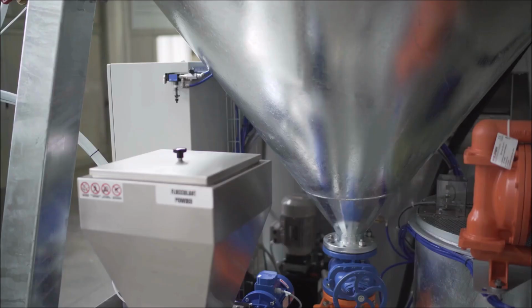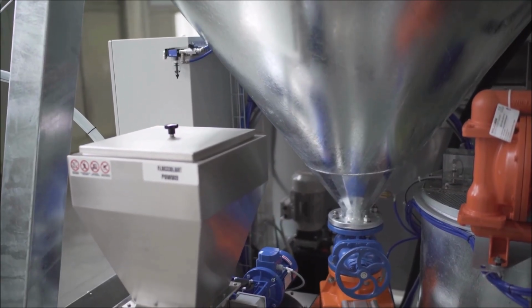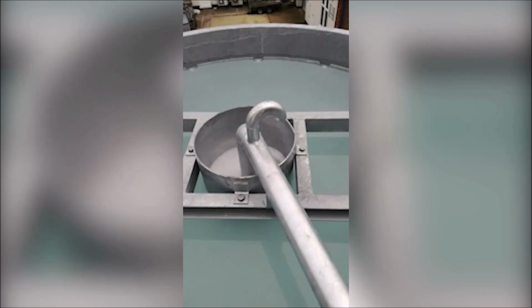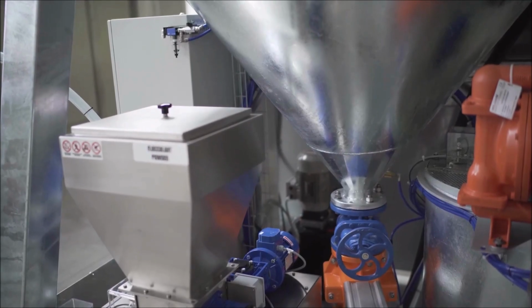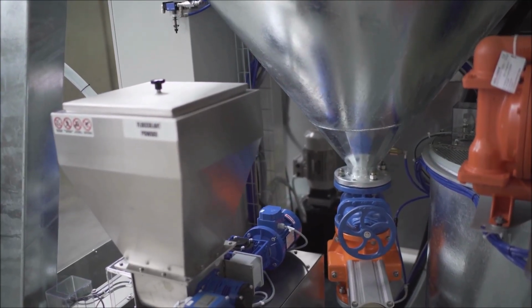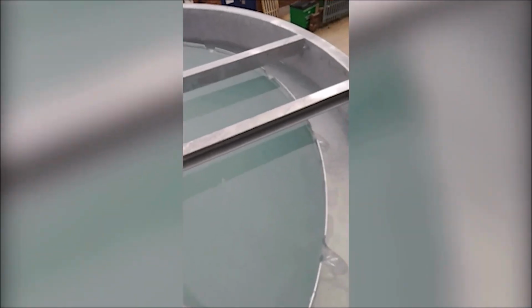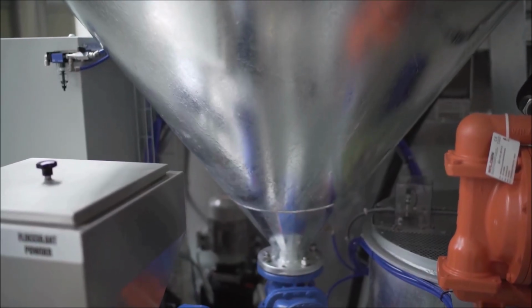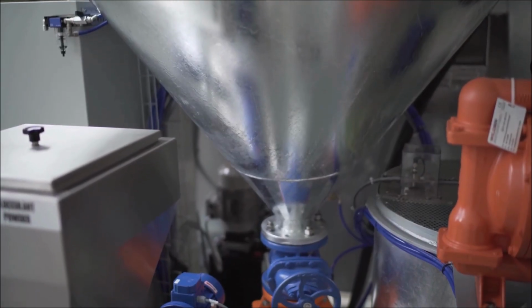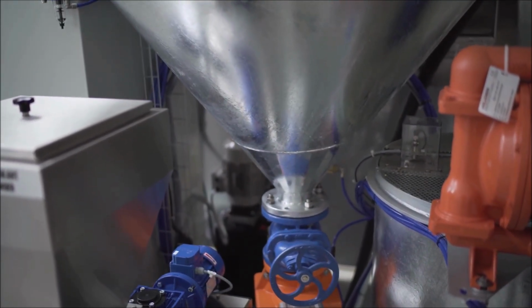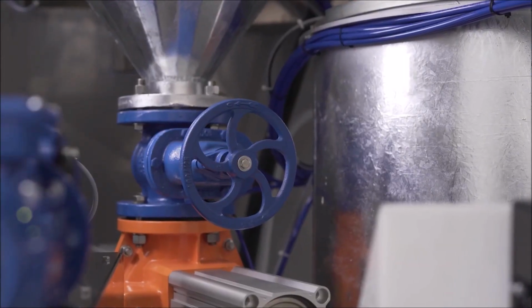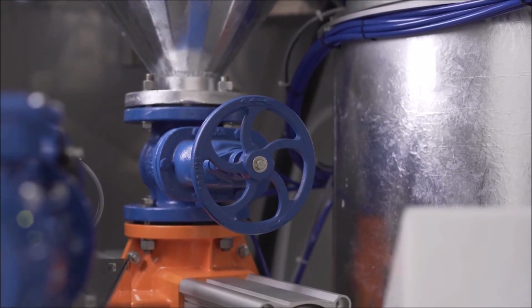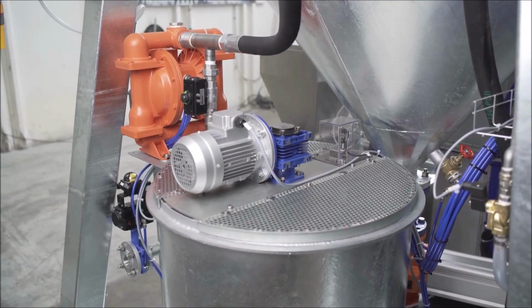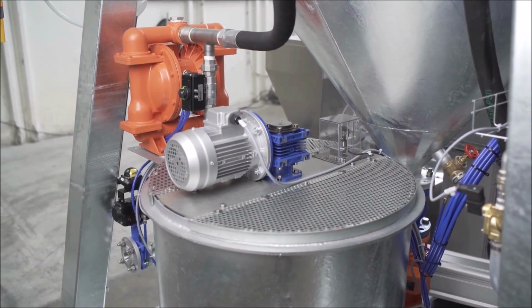This clarification process allows us to obtain a compact sedimentation of the sludge at the bottom of the decanter. At the same time, in the upper part, only the clarified water remains, which through the overflow hole is conveyed to a special storage tank. This water is then ready to be brought back to the machines installed in production. The sludge accumulated at the bottom of the decanter is ready for the second process managed by the plant, namely dehydration with filter press. Through a pneumatic valve, the sludge is discharged in a completely automatic and controlled manner and is conveyed to a dedicated tank, where an agitator ensures proper homogenization in preparation for the following pressing.